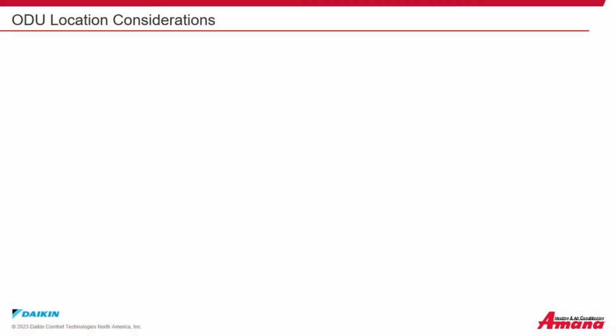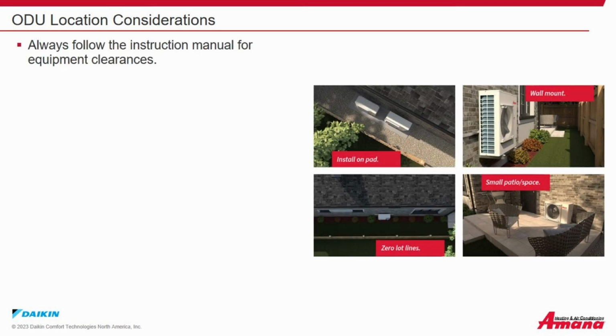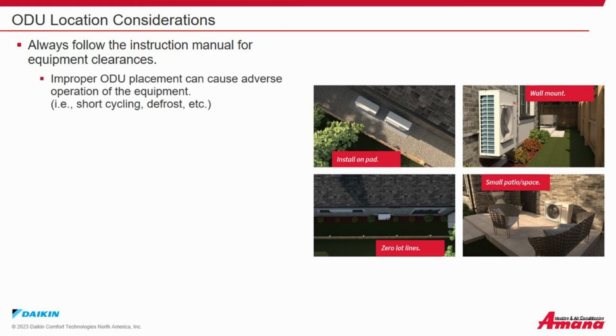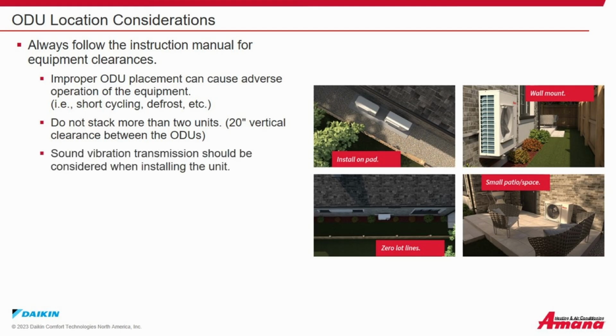Outdoor unit location considerations. Always follow the instruction manual for equipment clearances. Improper outdoor unit placement can cause adverse operation of the equipment, for example, short cycling, defrost, etc. Do not stack more than 2 outdoor units, with at least a 20-inch vertical clearance between the outdoor units. Sound vibration transmission should be considered when installing the outdoor unit.